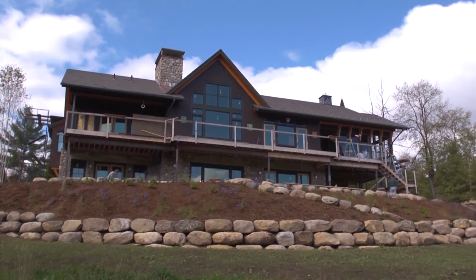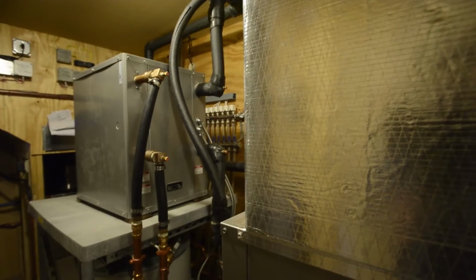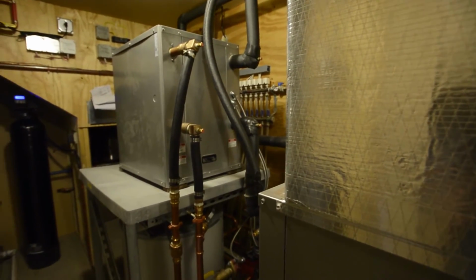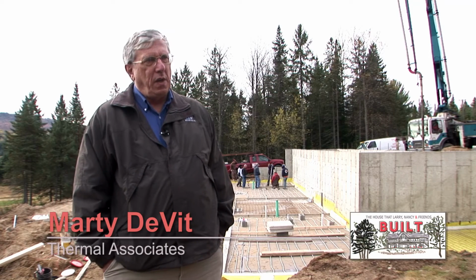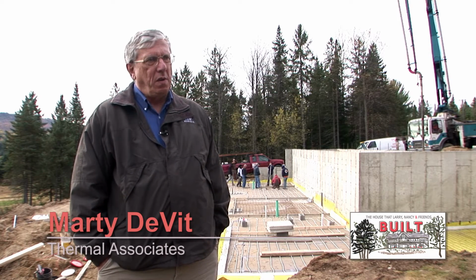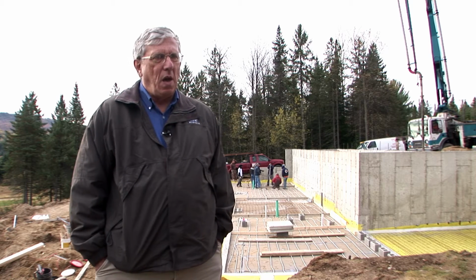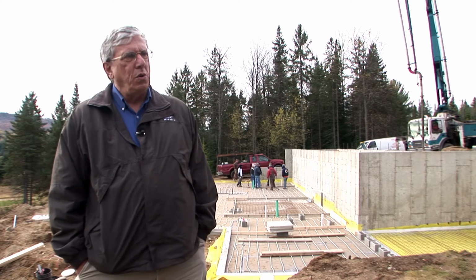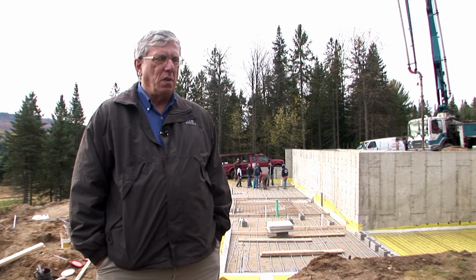The most we can get out of using electrical energy is to use a ground source heat pump. That will not be the right solution in every condition, but in a very cold climate especially, it's a particularly apt solution. We're going to drill a well 500 feet deep, and we're going to put a 1.25-inch pipe to the bottom of it and back out. And we're going to circulate in that an alcohol and water solution. The alcohol is to prevent freeze-ups and off-cycles.